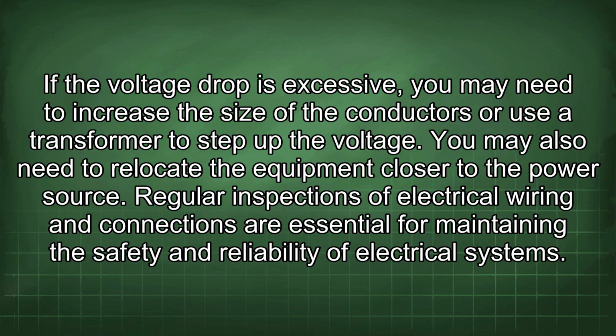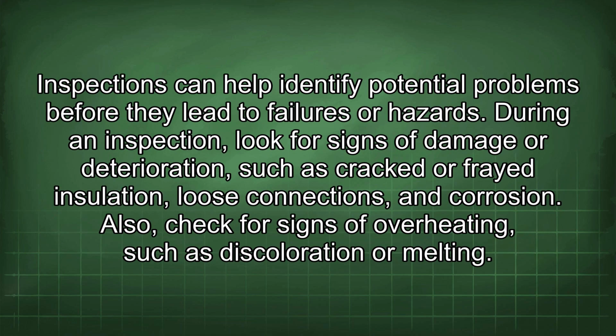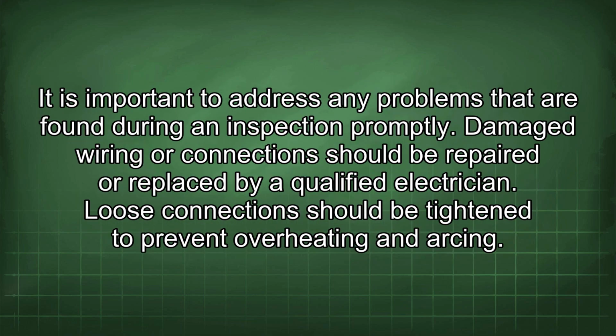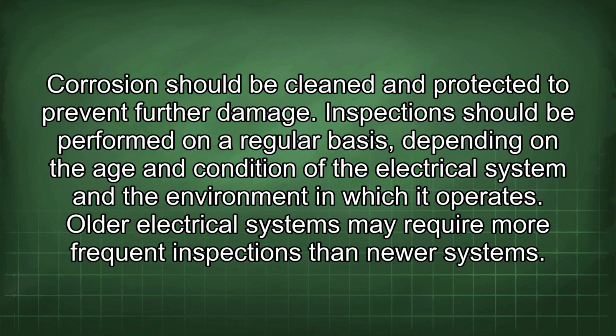Regular inspections of electrical wiring and connections are essential for maintaining the safety and reliability of electrical systems. Inspections can help identify potential problems before they lead to failures or hazards. During an inspection, look for signs of damage or deterioration such as cracked or frayed insulation, loose connections, and corrosion. Also, check for signs of overheating, such as discoloration or melting. It is important to address any problems that are found during an inspection promptly. Damaged wiring or connections should be repaired or replaced by a qualified electrician. Loose connections should be tightened to prevent overheating and arcing. Corrosion should be cleaned and protected to prevent further damage.